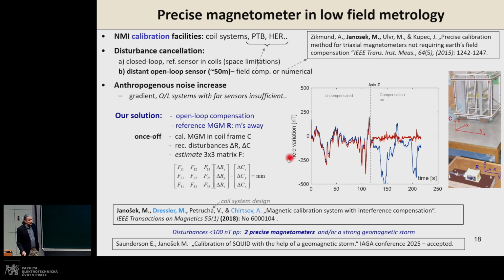And I have 2 slides more about precise magnetometers in low field metrology, because this is the other topic of my talk. We have tried to improve the coil systems which exist at the National Metrology Institute. Our approach is not to use a closed loop sensor or a distant open-loop sensor, for example, 50 meters away. Our approach is to use 2 sensors close apart, recalculate and realign the 2 sensors' orthogonal frames together by actually using the ambient noise.